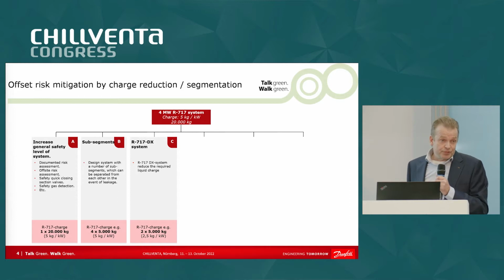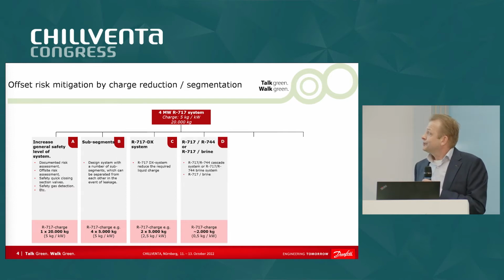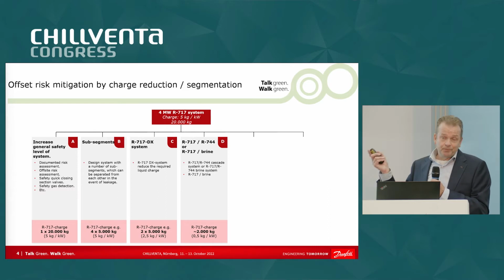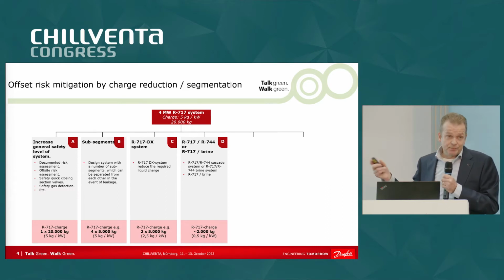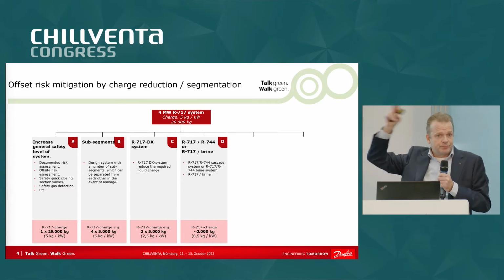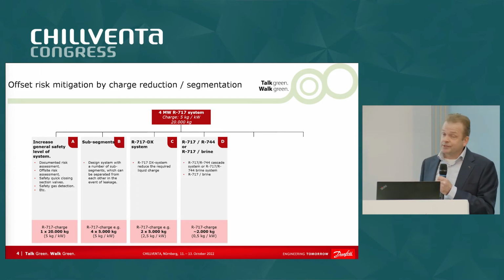Another way of reducing the charge is ammonia DX, because then you don't have the flooded part in the suction line. You can go really down in charge. So for instance, here you could go to half of the charge. A very popular system is the cascade system. So ammonia on top, small system, small charge, high capacity, CO2 pumped around in the second stage. Very popular, very robust. You save a lot of ammonia, to be honest, in charge.